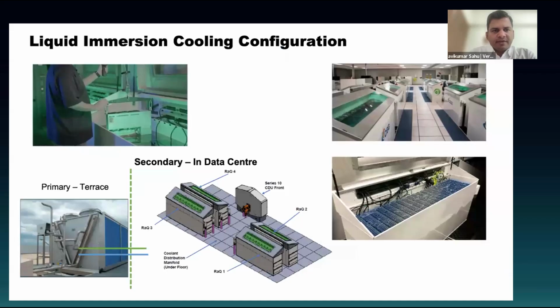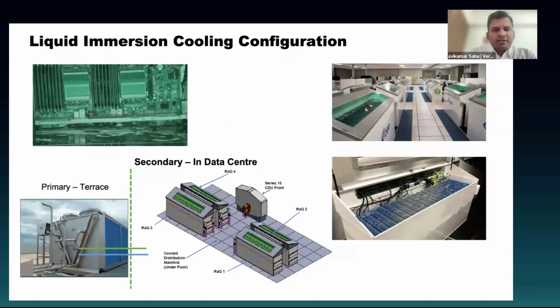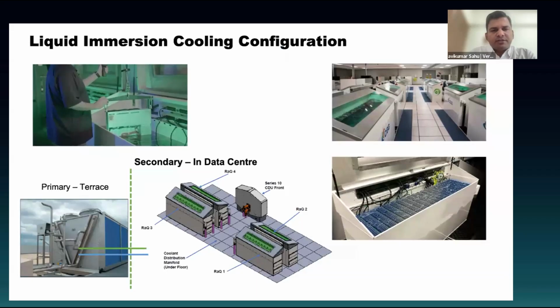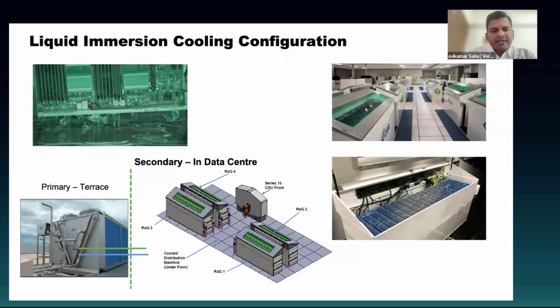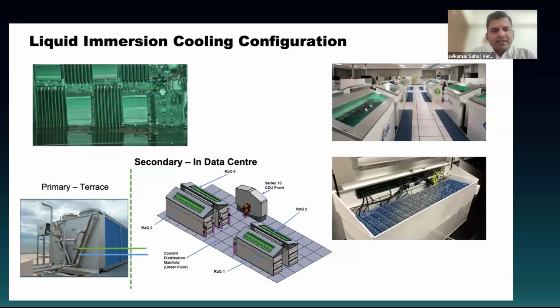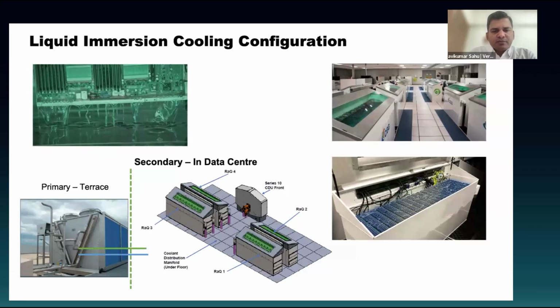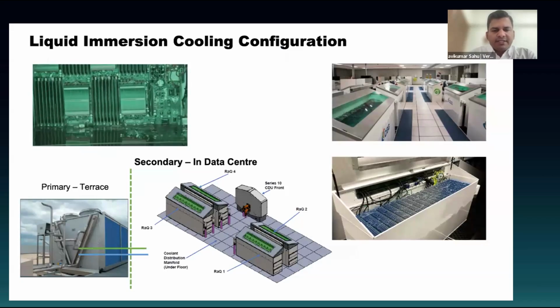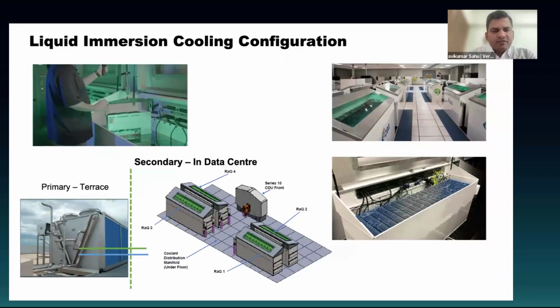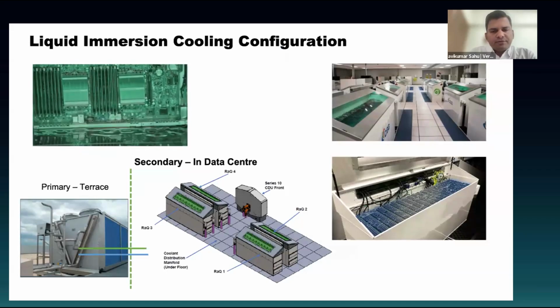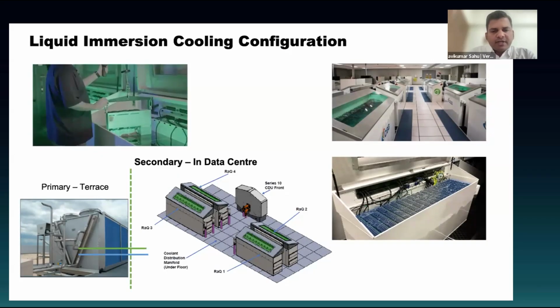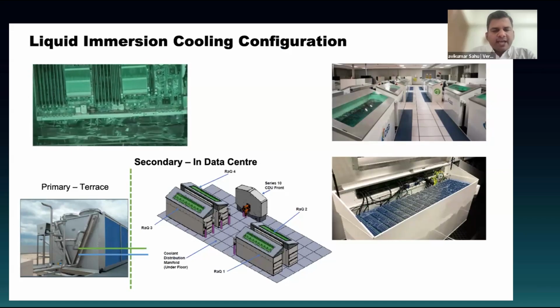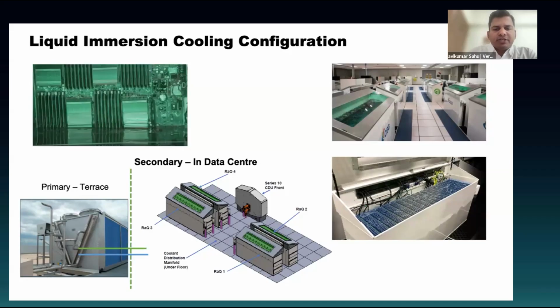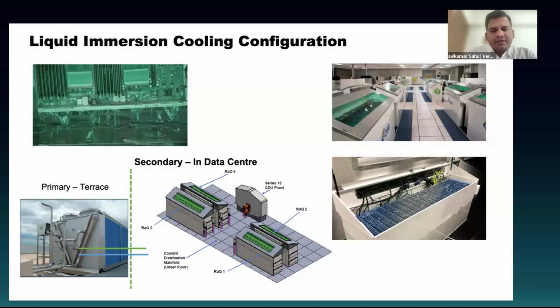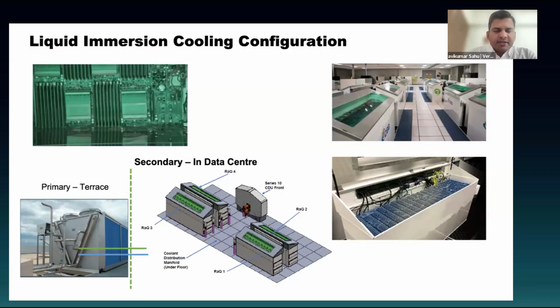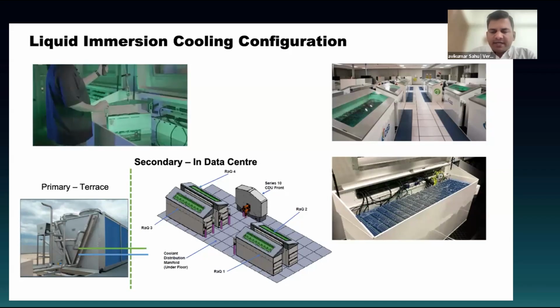Now coming to immersion cooling. We have seen direct to chip. Liquid immersion cooling is basically where we submerge the entire server into the liquid. You can see in the image, it has a tank. Each tank is in the size of 42U or 48U or 52U. So either 2 tanks, 3 tanks or 4 tanks, based on your rack density. It has multiple tanks associated with one single CDU, and heat rejection is through your dry coolers.